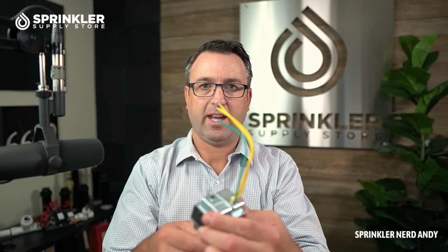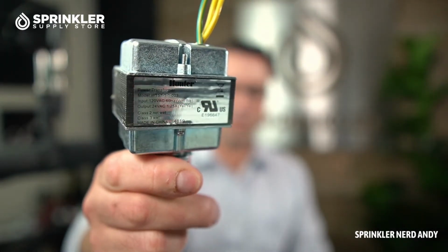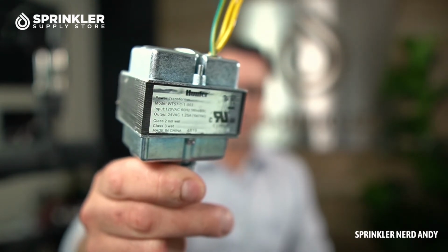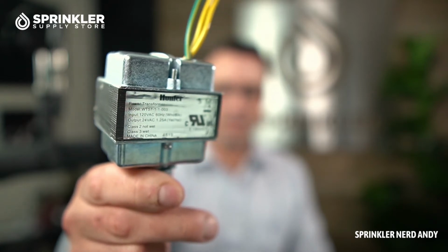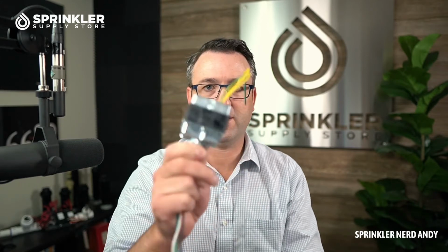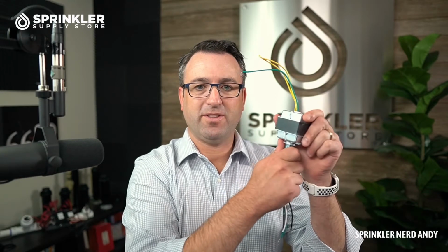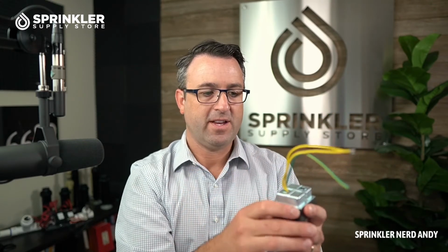Okay, now let's take a look at what we would consider more to be an outdoor transformer. Let me preface that: the one before is for an indoor controller, because the transformer is external, so it plugs into the wall. You would not plug this into a wet environment outdoors. Outdoors, you wouldn't plug any transformer in. The transformer is located inside of the controller, and it looks more like this. This is an internal mounted transformer, and again, you can see the specification of this: 120, 60 hertz, and does this say the wattage? This says amps, but you can sometimes work backwards too. So this is an internal transformer that is built into the controller. Generally, you would have electrical conduit coming up into the control box, and this is typically inside of another casing around it. So you might have to take the cover off and then you can remove it.